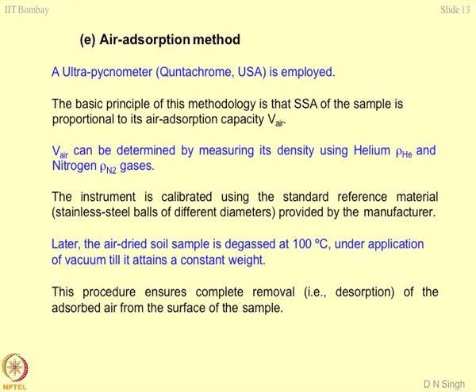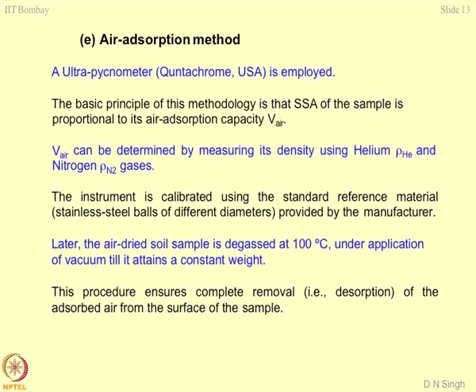This instrument is calibrated using standard reference material — stainless steel balls of different diameters. Steel balls have the smoothest surface, so there should be almost no adsorption of gases on them, making them a reference mark where adsorption is nearly nil. Later, the air-dried sample is degassed at 100 degrees centigrade under vacuum until it attains constant weight. This procedure ensures complete removal — that is, desorption of adsorbed air from the surface of the sample.